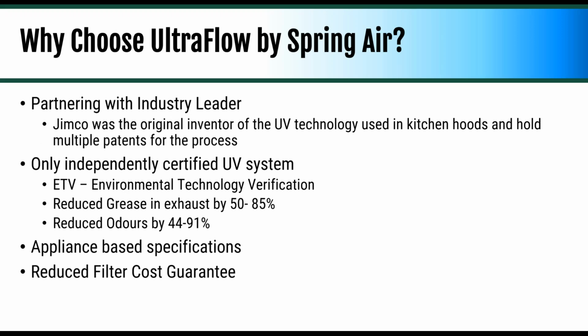So why choose SpringAir? There have been UV hoods in the system for a long time. I'll be honest, I wasn't a huge fan of them for a long time because they do require proper maintenance, and there wasn't a good solution in the market for different appliances. Some of the appliances, like a charbroiler, are really hot and have a lot of effluent. Heat makes UV less effective at breaking things down, and there just really wasn't enough UV in the hood to be able to properly do it.